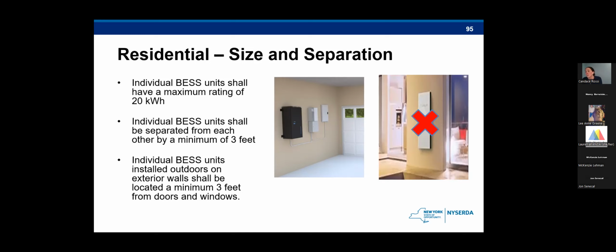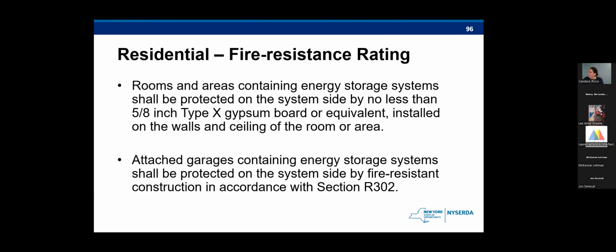And you can also notice the installations we have on the screen. The one with the X through it is wrong because you cannot install energy storage within living spaces, as much as some companies would want us to. No matter how cool they look, they definitely should not be installed within living areas. And the other one is in the garage and is installed properly, but may still require other features that are not in the picture.